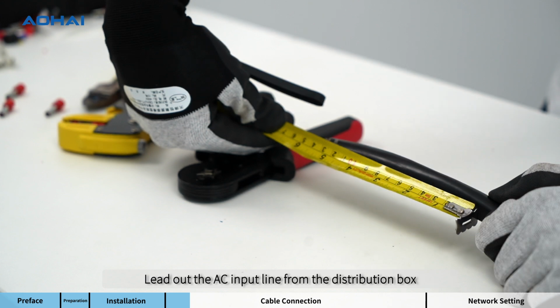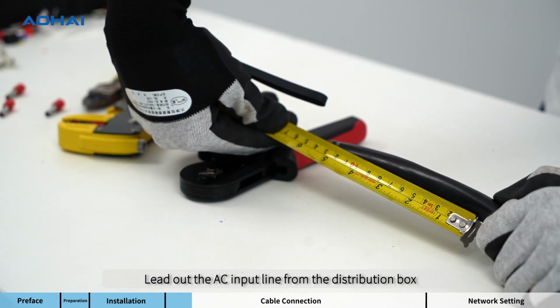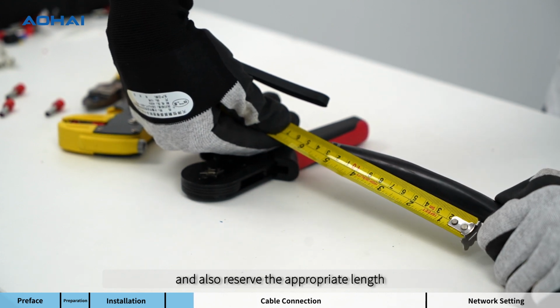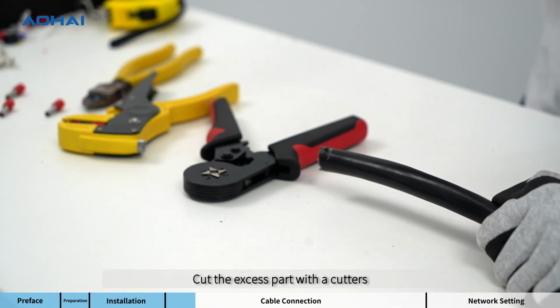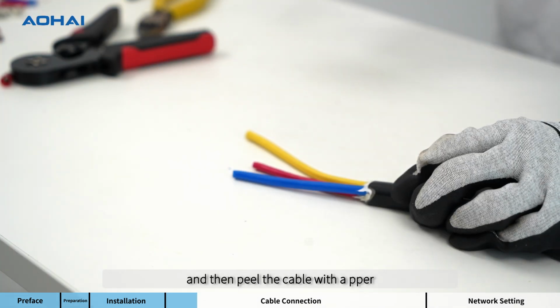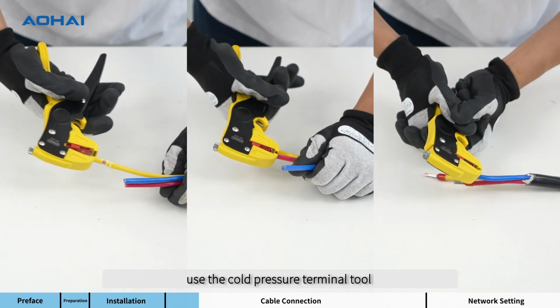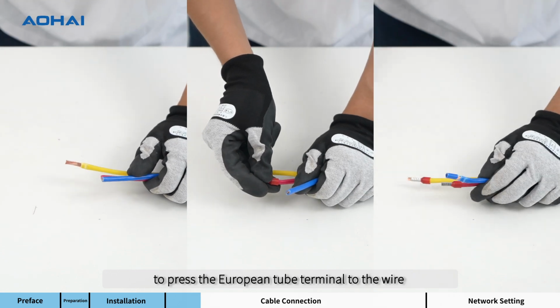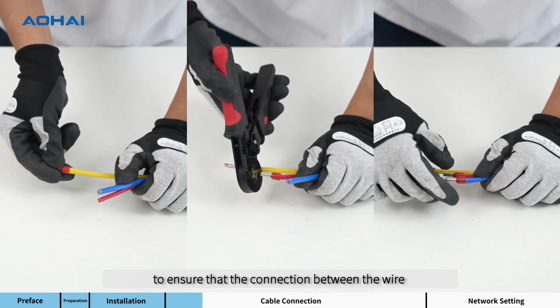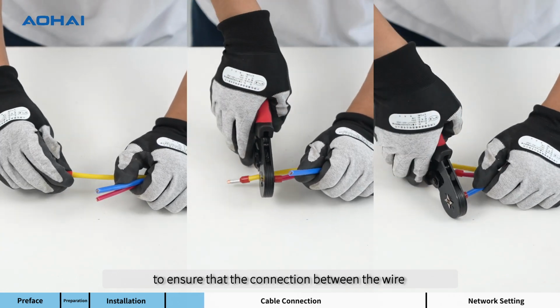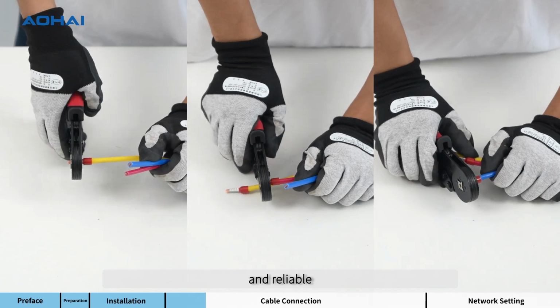Lead out the AC input line from the distribution box, and also reserve the appropriate length. Cut the excess part with the cutters, and then peel the cable. Finally, use the cold pressure terminal tool to press the European tube terminal to the wire, to ensure that the connection between the wire and the terminal is stable and reliable.